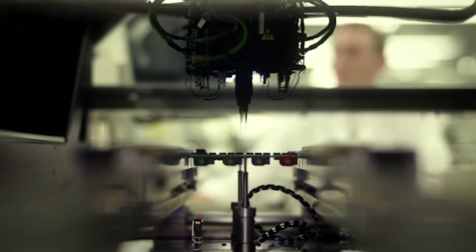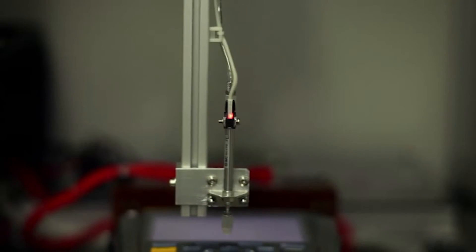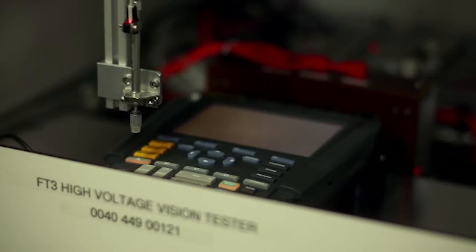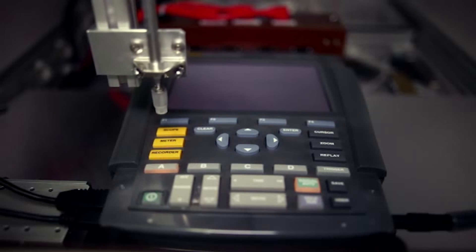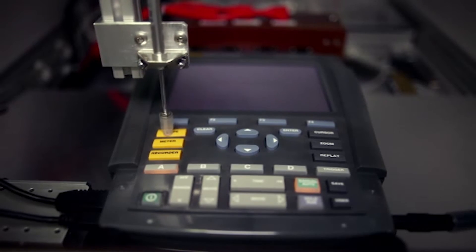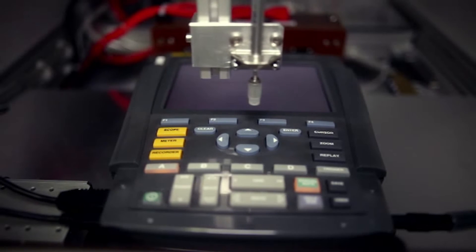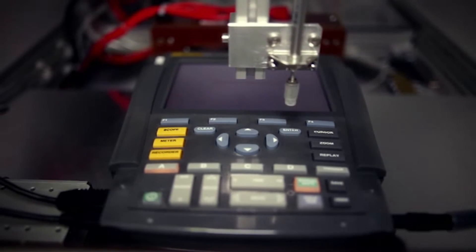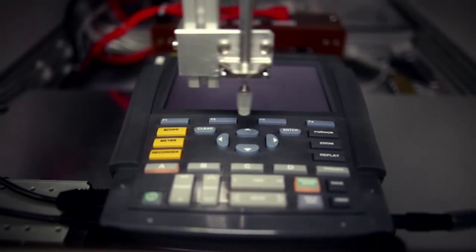During the implementation of the instrument's firmware, we set up a test that we run 24 hours a day, seven days a week. It's an automated test that presses the keys of the instrument.